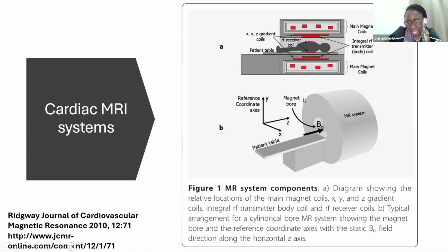So we now have a patient on the table within the bore. You have sort of 3 magnetic systems. You have the main magnet coils that are within the bore, and they exert the field intensity, and they are static. They don't move in principle. Then you have your gradient coils, your X, Y, and Z gradient coils for those X, Y, and Z axes. Now, these are not permanently on, and you switch them on and off depending on what your overall imaging destination is.